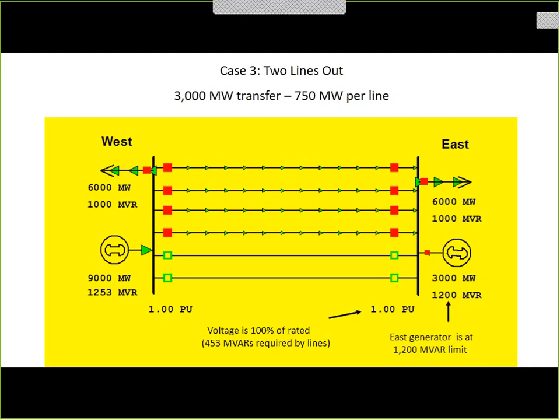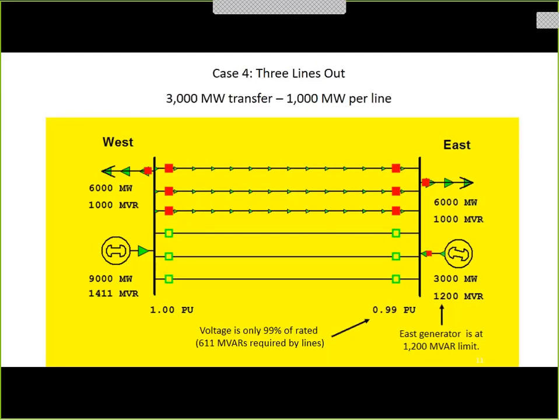Take out a second line. That power gets transmitted. Still 3,000, but it's 750 per line now. The VARs that it takes over here to keep the voltage at 1 has hit the limit at 1,200. So it's right at the edge of losing control of the voltage. And other than that, everything is okay. But that's still okay. I mean, 1 per unit is good, right? And we're just assuming that they're not thermally overloaded. They got a third line.